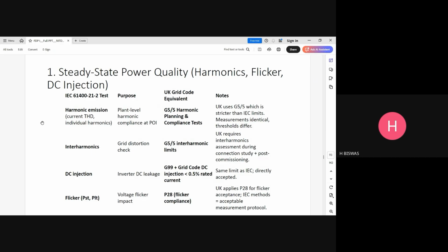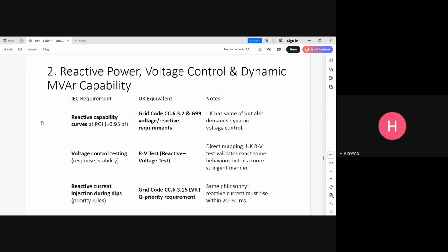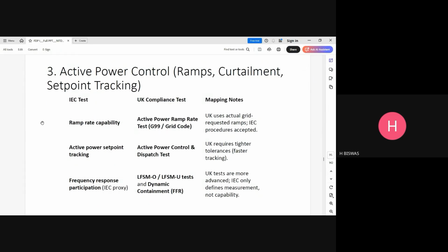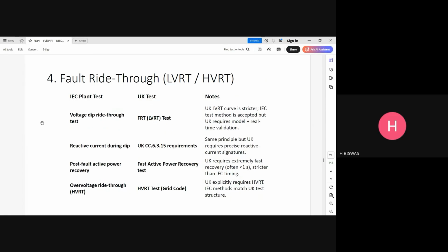So this is a quick comparison. On the left-hand side, this is the IEC 61400 series for the requirement. But the UK grid code equivalence has some specific clauses, and it is quite stringent. And what is the difference for them? A quick note is given. And of course harmonics, THD is there, interharmonics, DC injection, flicker, reactive capability, voltage control testing, reactive current injection, dips. So these are all parts of that. Ramp rate capability, and then active power set point tracking, IEC proxy. So these are some of the things. So LVRT, HVRT, again, the IEC plant test and UK test are quite different, just to give you a flavor. So that's how the system has been developed in that particular country and how it works.